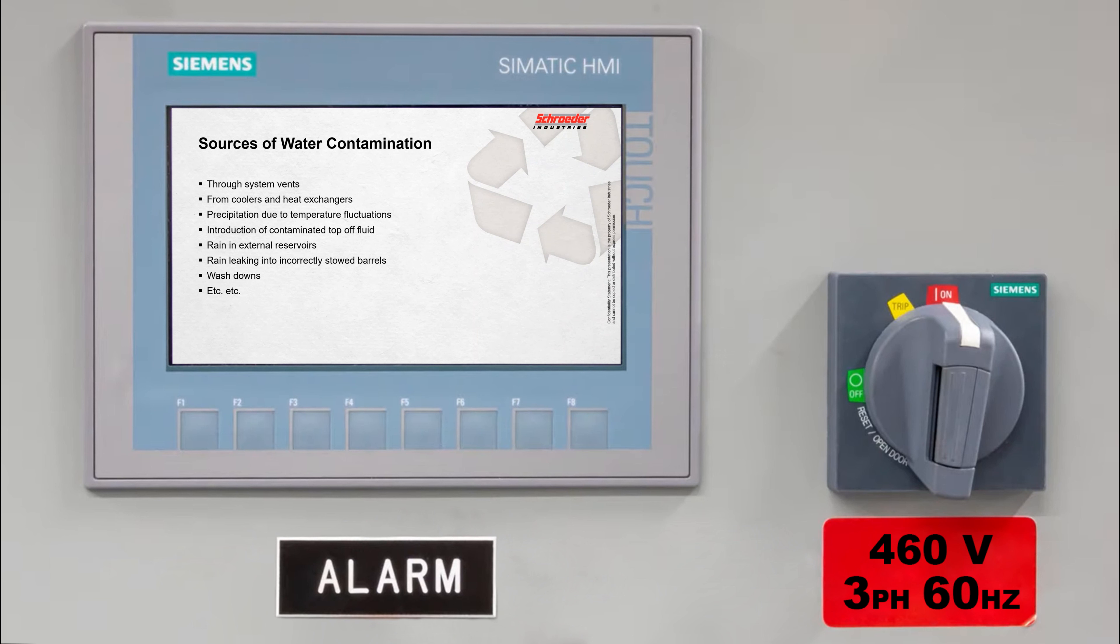But what we also want to do when we sell these units is really find out where is the source of their contamination coming from. Do they not have sealed vents on the tank? Are they not using desiccant breathers? We get a lot of water coming in from coolers and heat exchangers. A lot of times the customer will be running this unit to keep their system operational until they can replace their coolers.